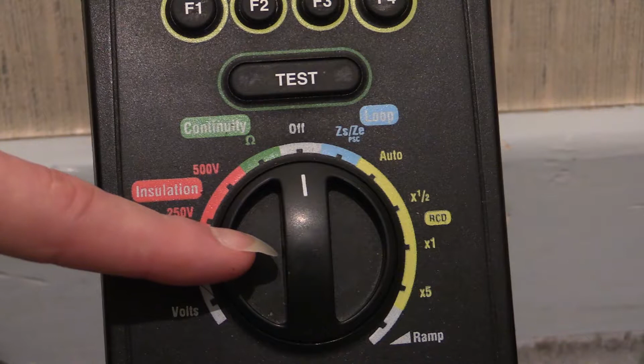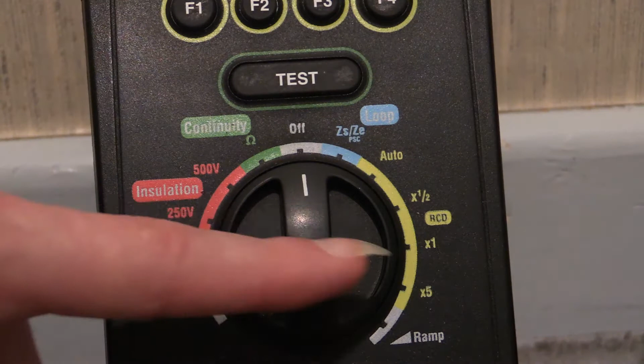You shouldn't really use this for verifying whether a circuit is alive or dead, because there's always this option that if you're using it for that and you accidentally get this on the wrong setting, you might find that you'll either blow the tester up or you'll verify a circuit which you think is dead but it is actually live, and you then proceed to take that circuit apart and be electrocuted - because you got this dial in the wrong position when you proceeded to carry out that test.